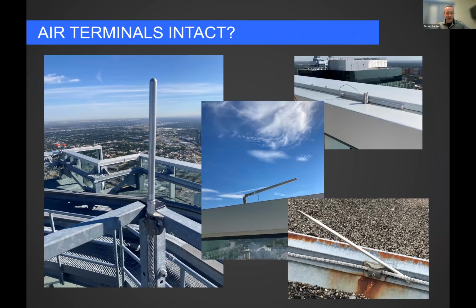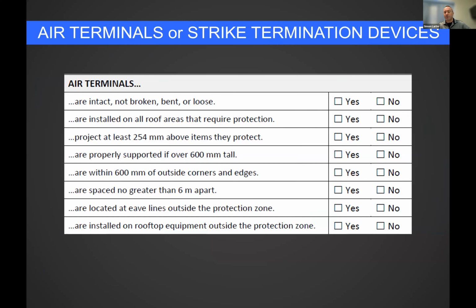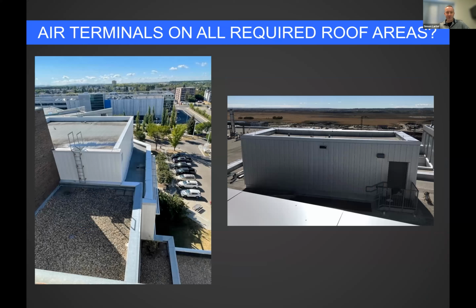Results, folks. Air terminals - are they installed on all roof areas that require protection? Here's a tale of two hospitals. On the left is Red Deer Hospital - it's got some lightning protection on it, but it is not fully protected, only some of the roof levels have it. The upper roof levels, where they've done additions to the hospital, you see that white-clad penthouse or roof area has absolutely zero lightning protection on it. So on the checklist you check no, air terminals are not on all the required roof areas.